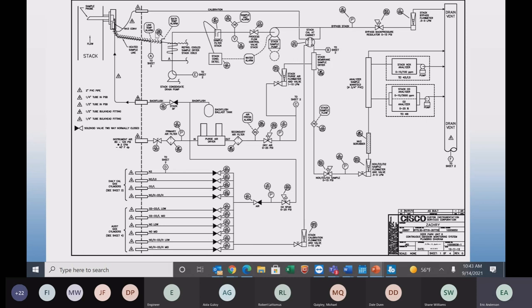We're talking about, hey, let's pull the heated sample line off, our 5/16 heated sample line. Cap it off, and again, we cap this off here at the cooler, zero flow here, zero flow here. If we don't, we can move to the filter, so we'll bypass the cooler here. So we'll cap it off there, and again, we should have zero flow here, zero flow here. You know, if not, let's look at this filter. Gasket, bowl, and again, that's a glass bowl, and if you drop it, you're going to break it. I've done it, so be aware of that. I'd keep a spare one of those.